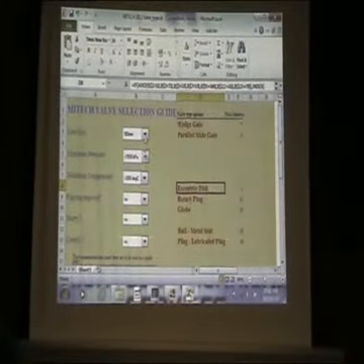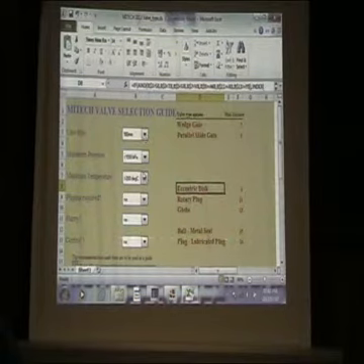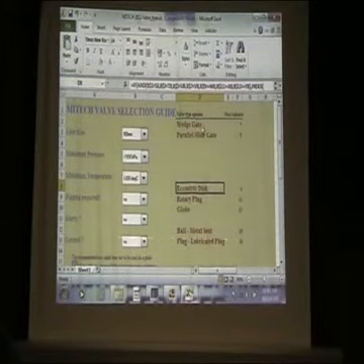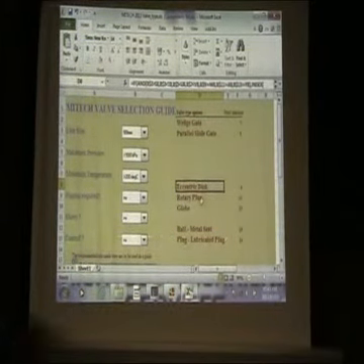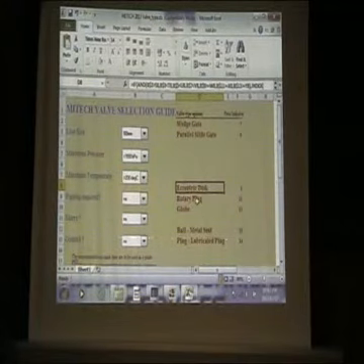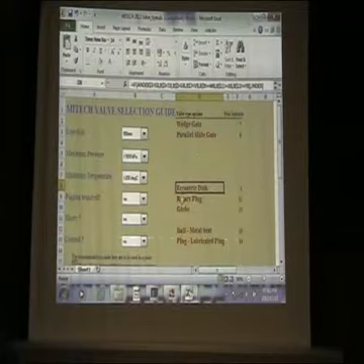Alright, so we got a 100 mm line size valve, we got less than 1000 kPa as per your applications. We're saying the maximum temperature exceeds 200 degrees, so you can only look at a gate valve, slide gate valve, eccentric disc, rotary plug, a globe valve, a ball valve, or a plug valve. Alright, that's the type of valves that you can look at.